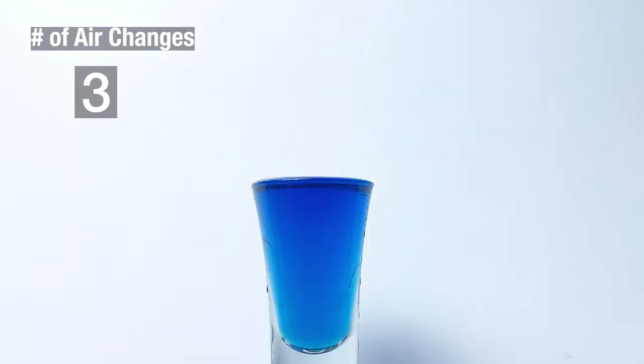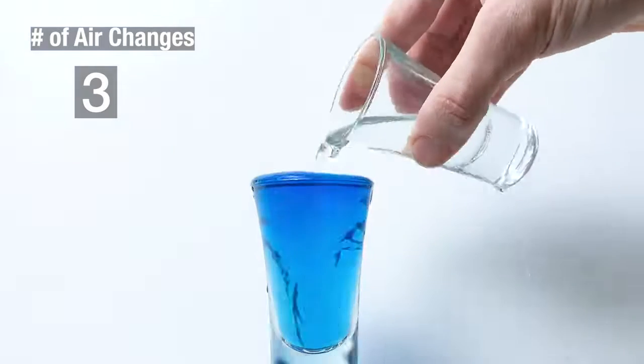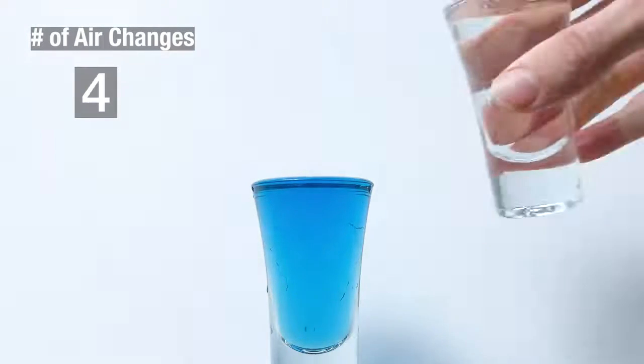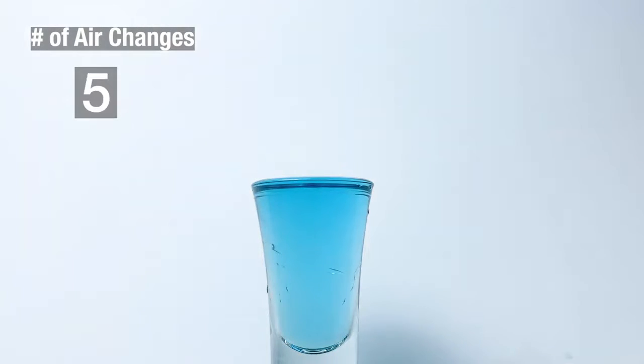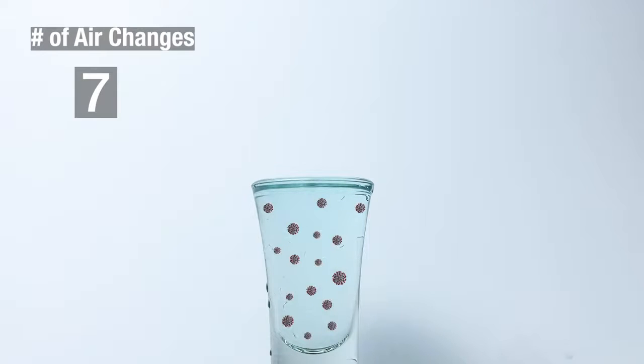Let's speed this up. Even after 4 or 5 air changes, there is still significant coloring. Only after 6 or 7 air changes does it start getting down to the barely noticeable point, and even then, you can still see some blue. Now imagine that that blue was infectious virus particles. Makes you think, doesn't it?